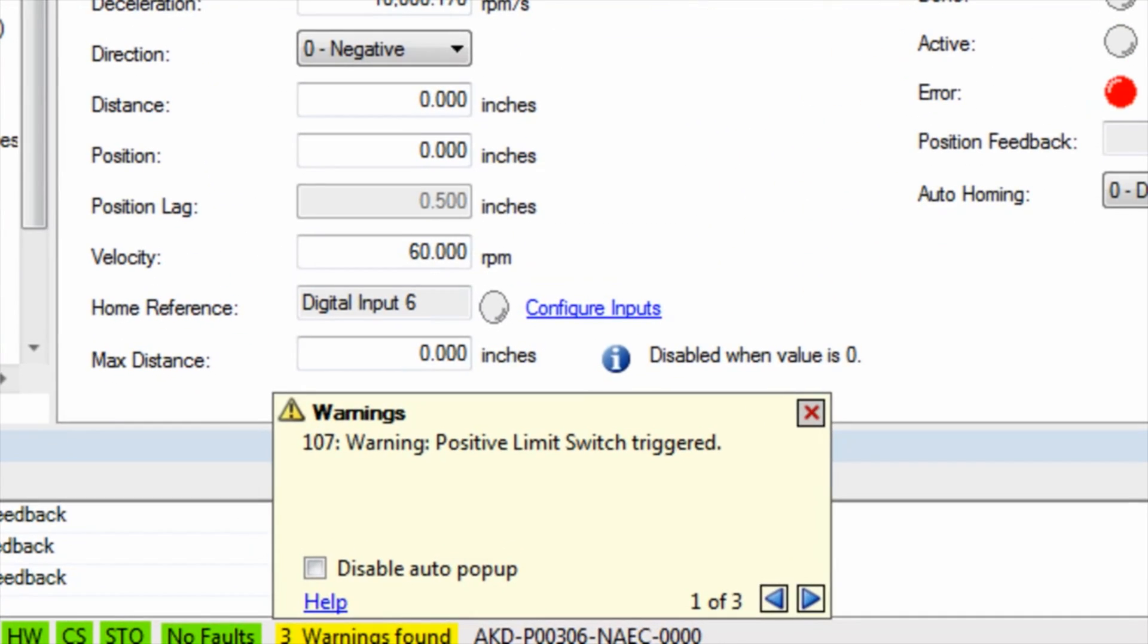If during the home sequence both the negative and positive end of travel limits are encountered, a fault will occur, indicating that the home reference was never found.